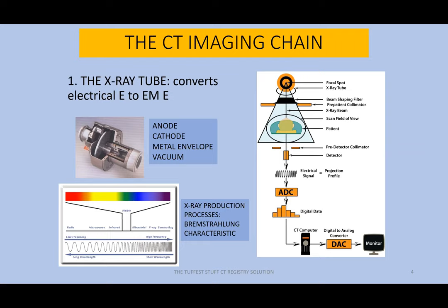As you know, electromagnetic energy is X-radiation. So the test answer here is: what's the function of the X-ray tube in the CT imaging chain? That function is the conversion of electrical energy to electromagnetic energy. The X-ray tube in CT, just like in diagnostic, has four major components.